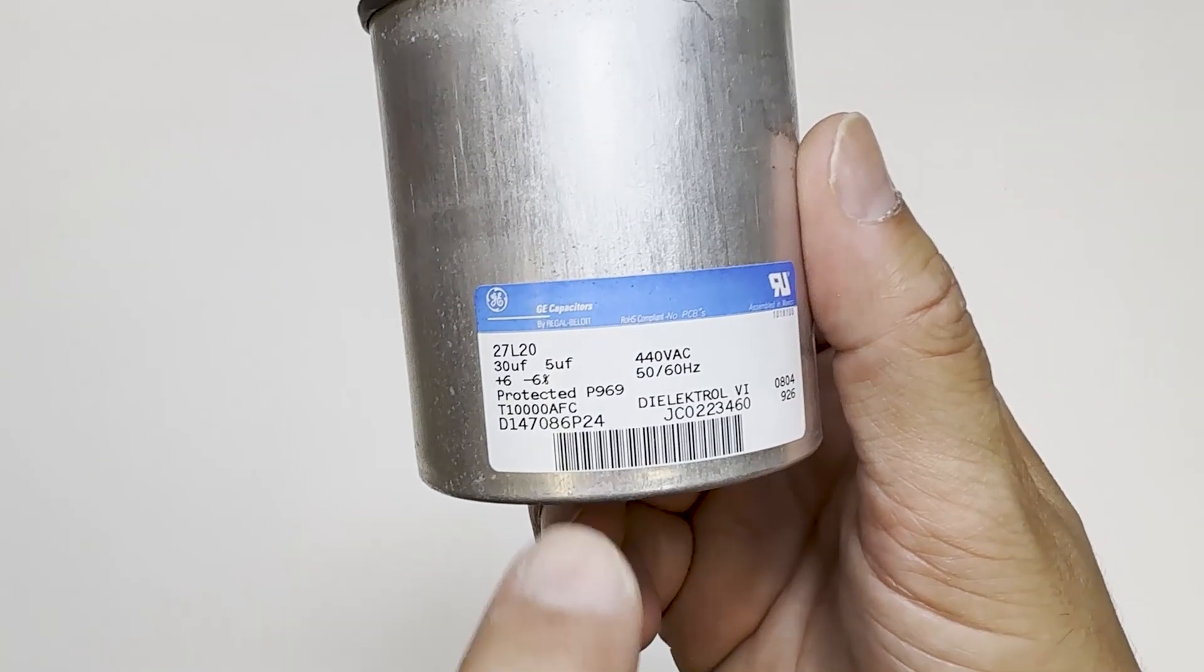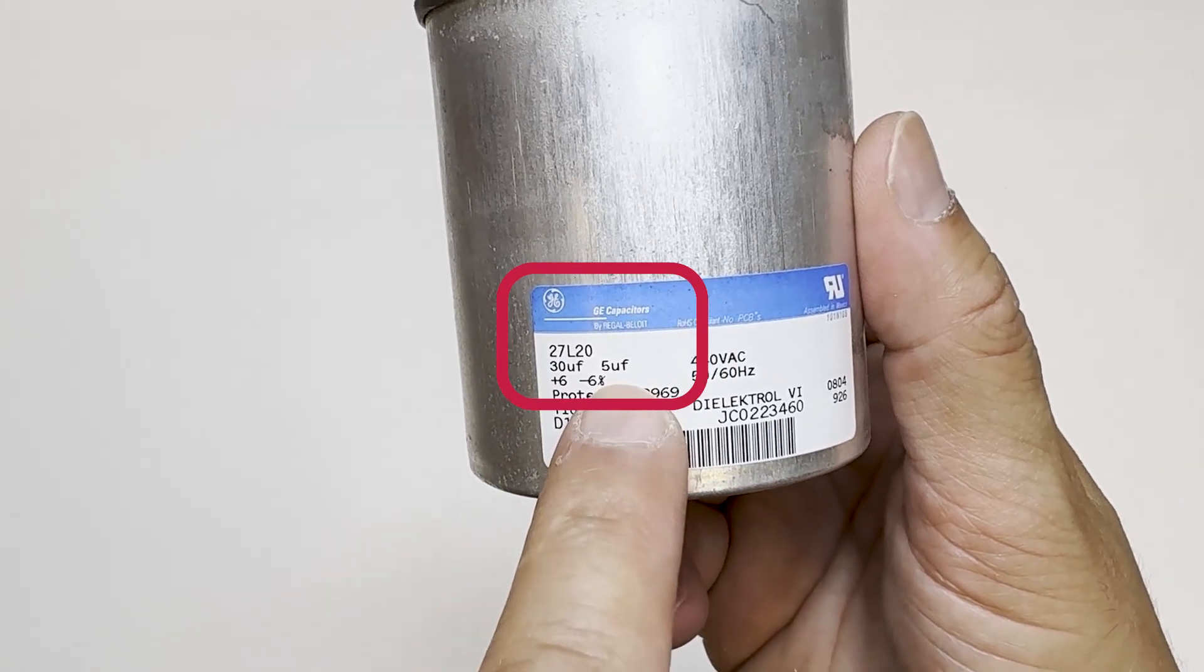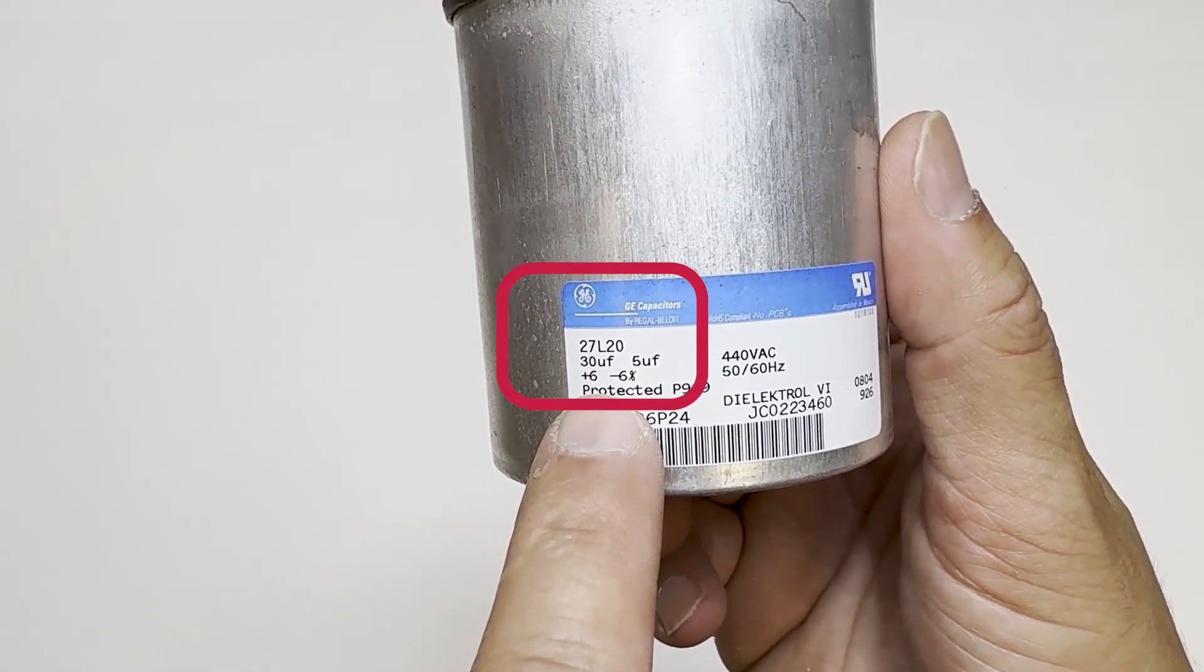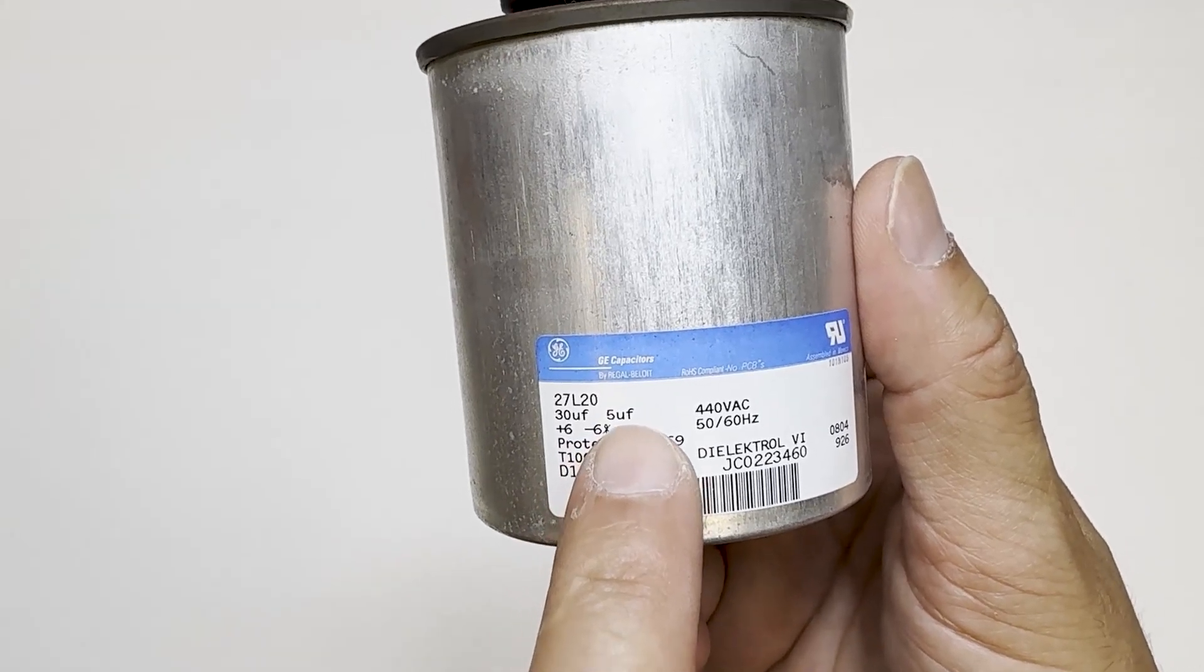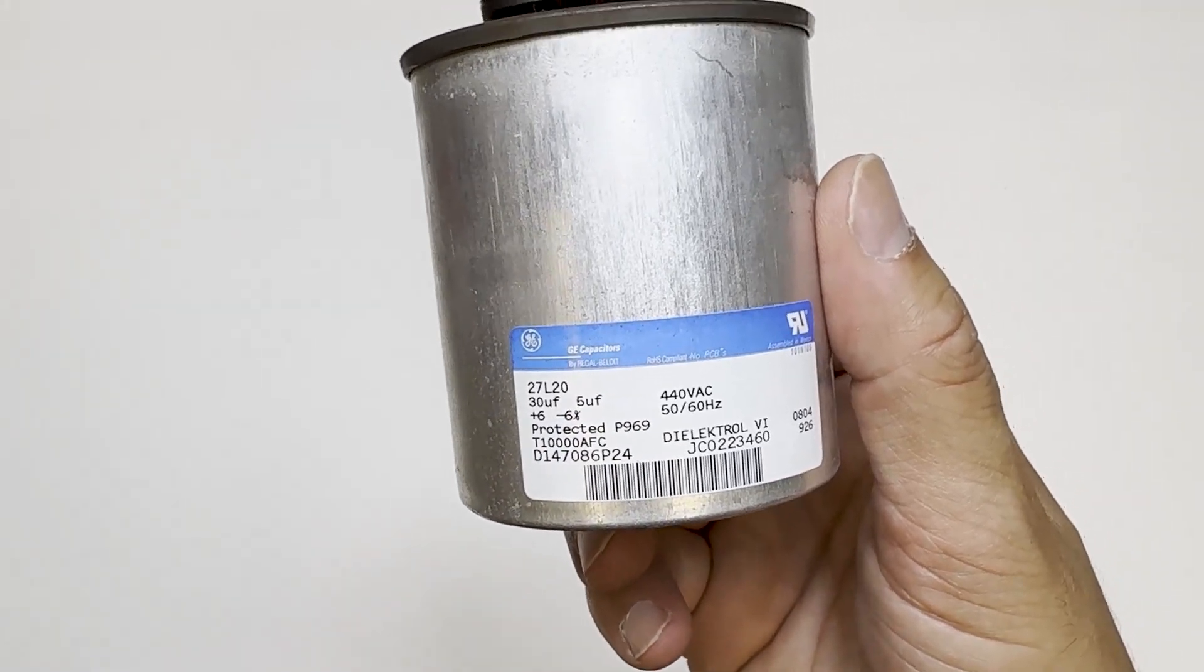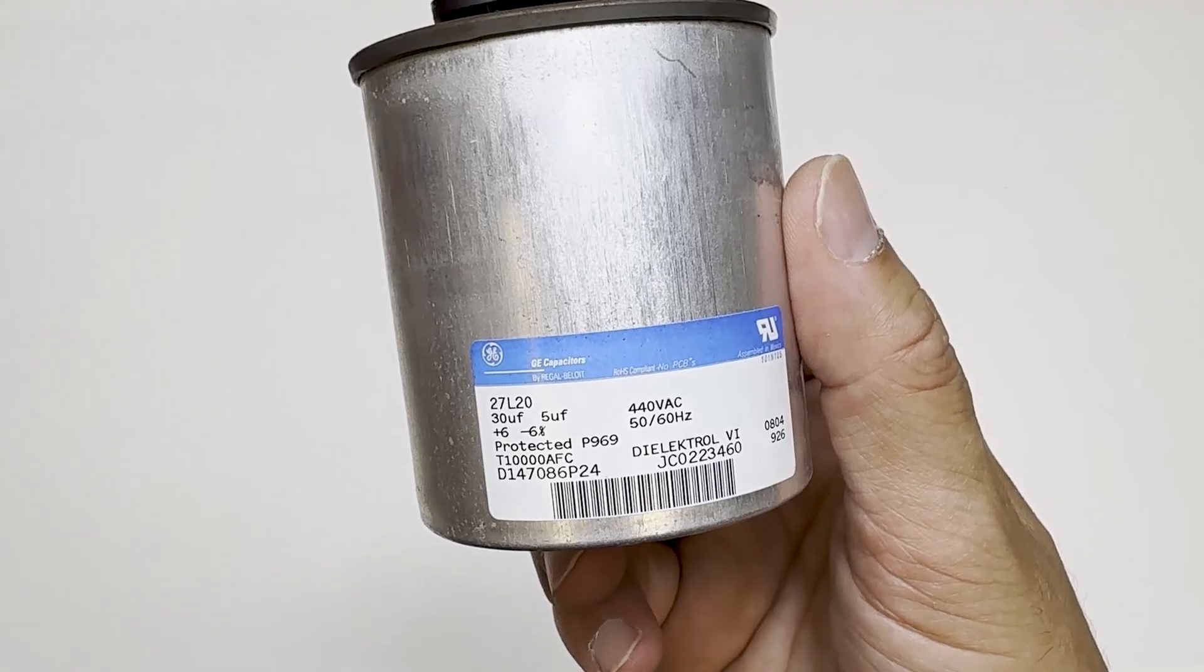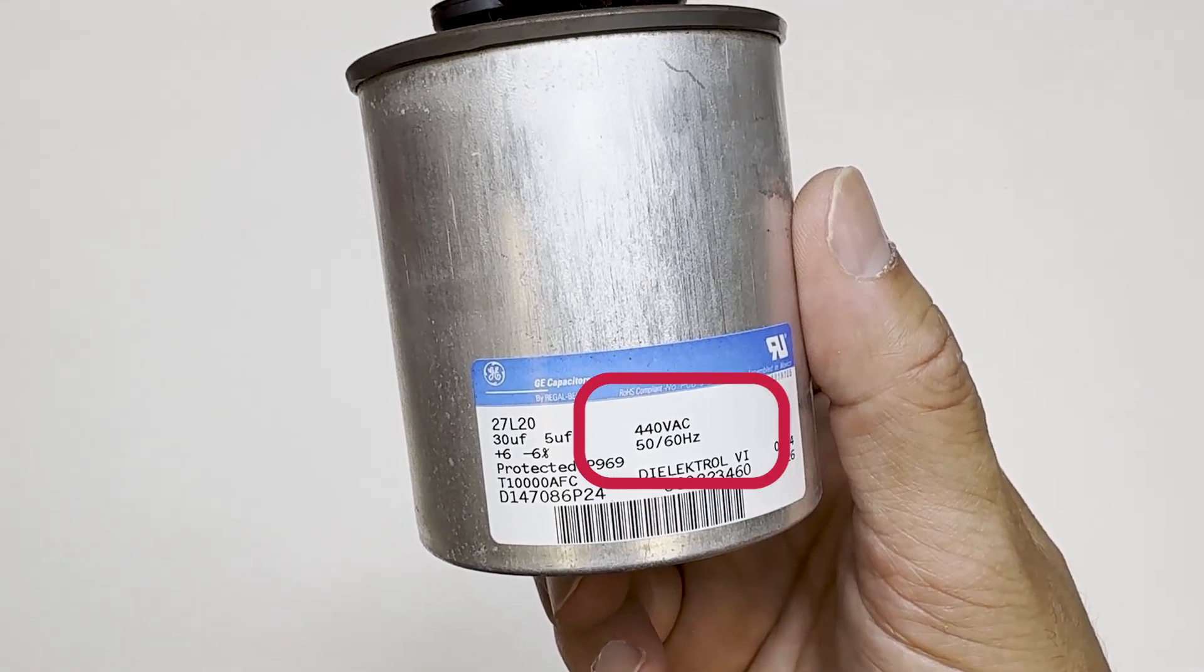Now let's look at the rating. It's labeled 30 by 5 microfarads. Meaning, 30 microfarads goes to HERM, the compressor, 5 microfarads goes to fan, and each gives you a tolerance of plus or minus 6%. We also have the voltages 440 and the frequency.